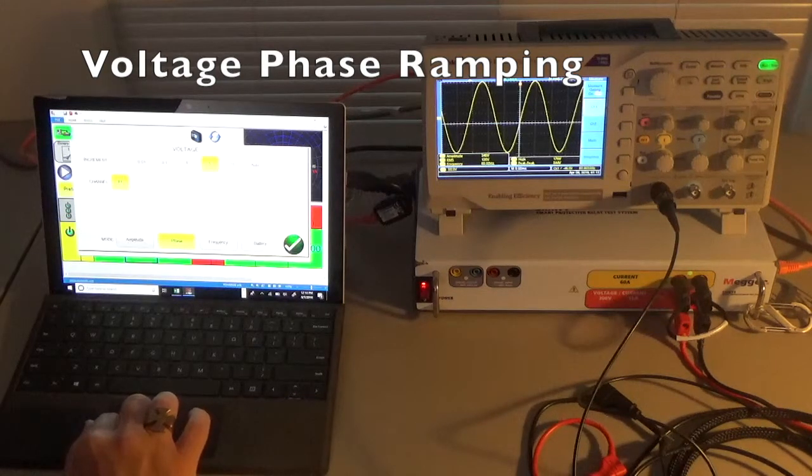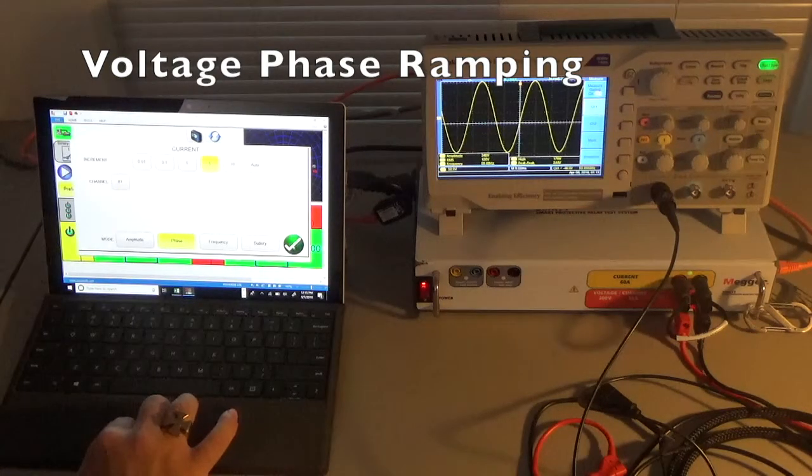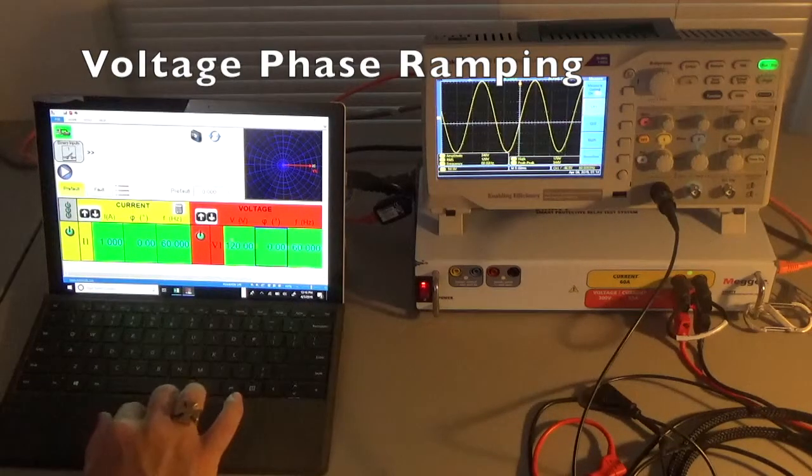Let's move the voltage phase to show the difference. Set up a ramp function on the voltage phase at five degree increments, channel 1, phase, voltage. Let's turn off the current ramp so we don't ramp both at the same time. The voltage phase is highlighted in blue. Ramping up: 50, 55, 60, 65, 70, 75, 80, 85, 90 degrees on the voltage phasor. Continuing to 180, then 270, and completing the circle to 360. Going back around the circle to zero — and we're back home. That's the phasor ramp up and ramp down for voltage and current with the SMRT1.